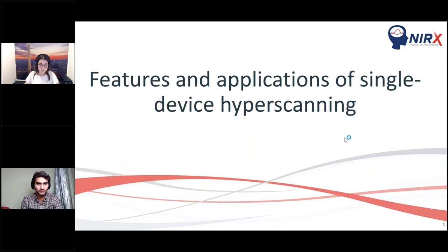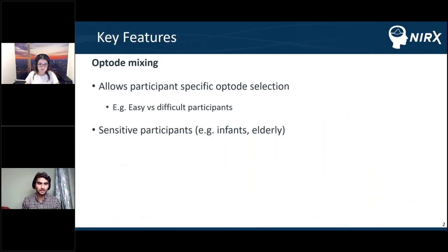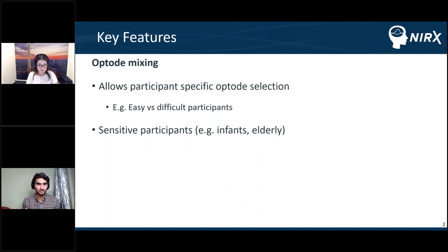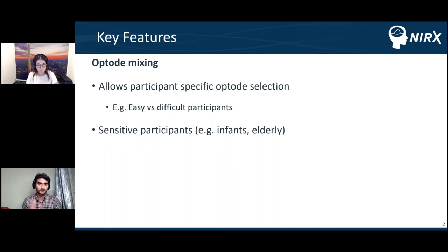Hyperscanning involves measuring different participants simultaneously, and there may be significant differences between these participants. For example, you may have one participant with dark, dense hair and another with less hair. We know that scalp-optode contact and light transmission is affected by hair color, thickness, and density. Using the same type of optodes might not be optimal — a one-size-fits-all approach for all participants in a hyperscanning experiment might not give the best signal quality or be optimum in terms of setup type.